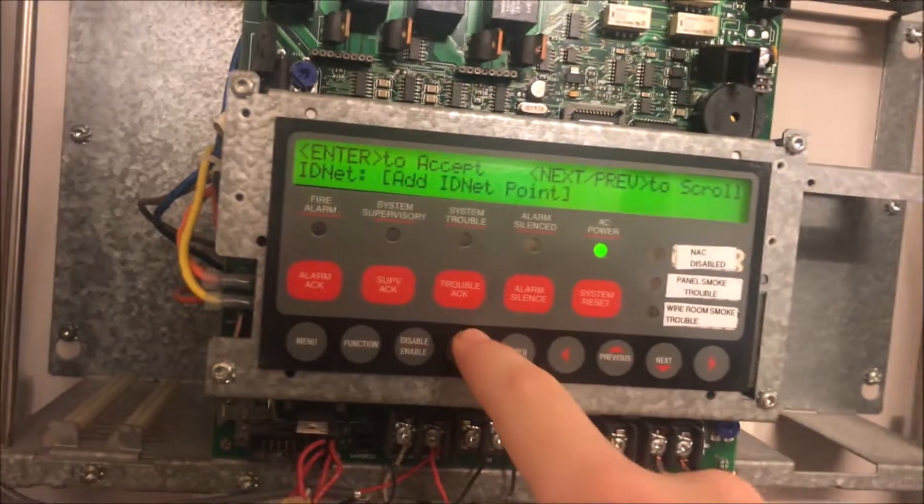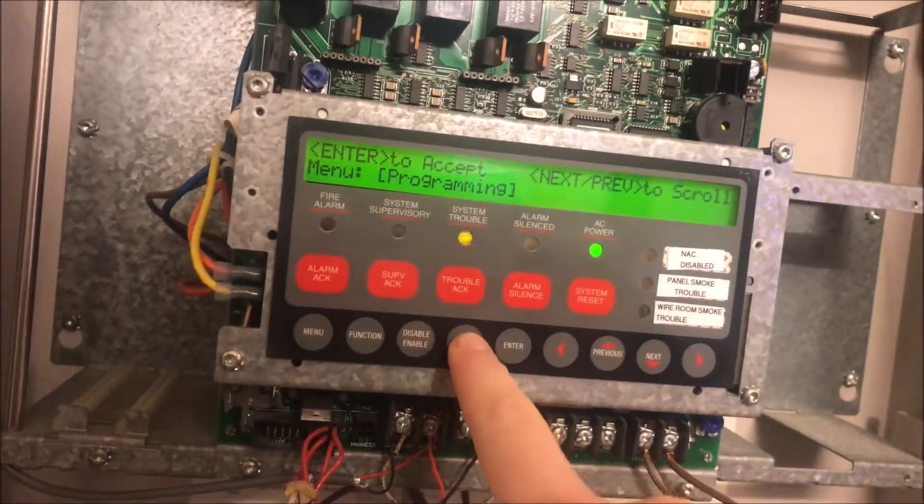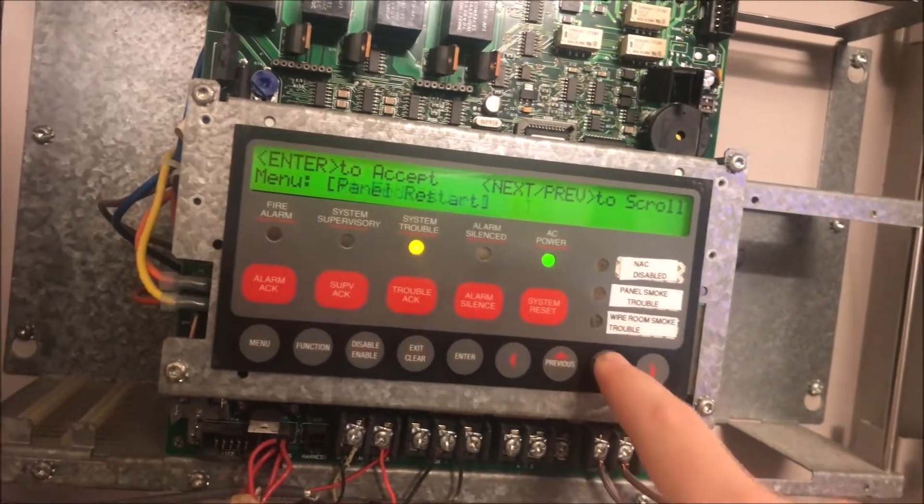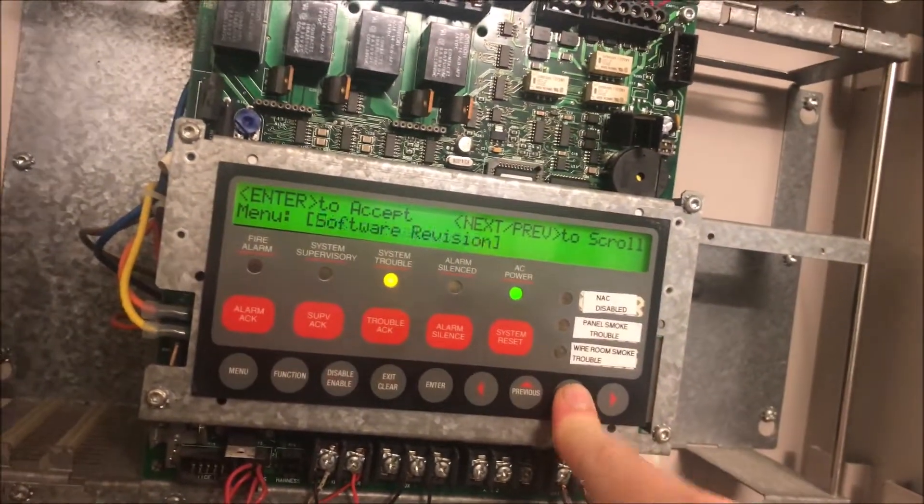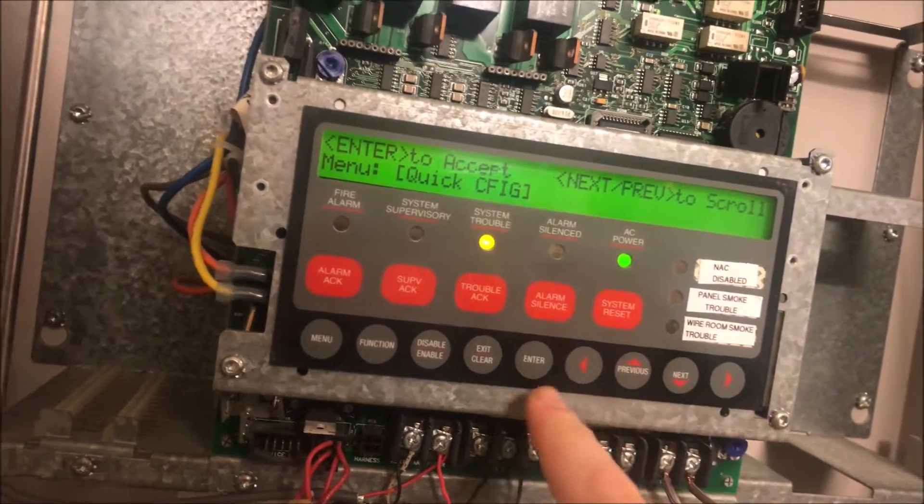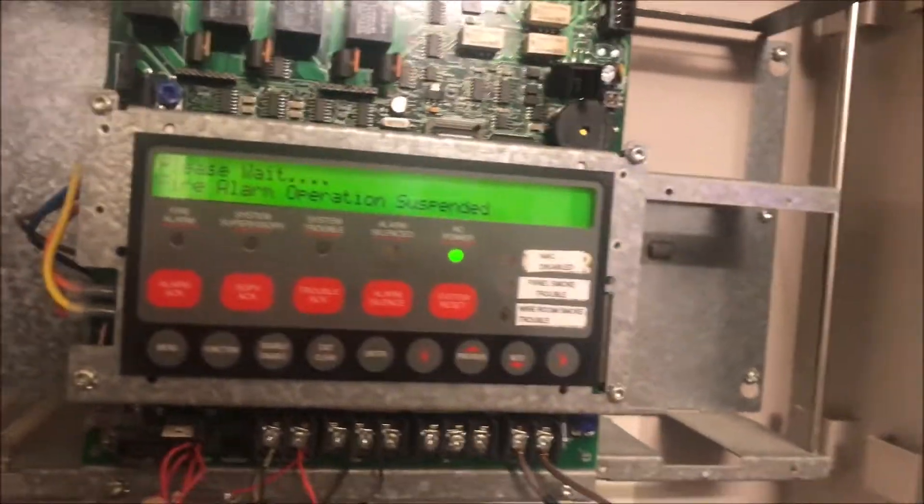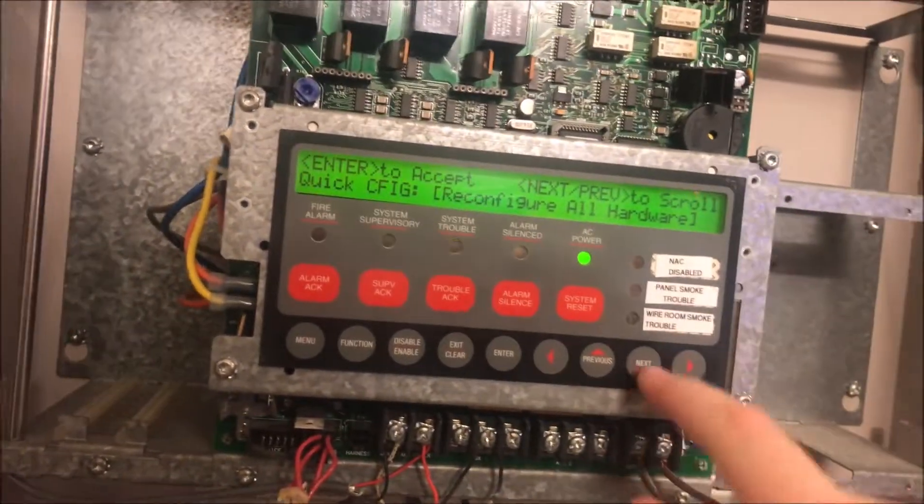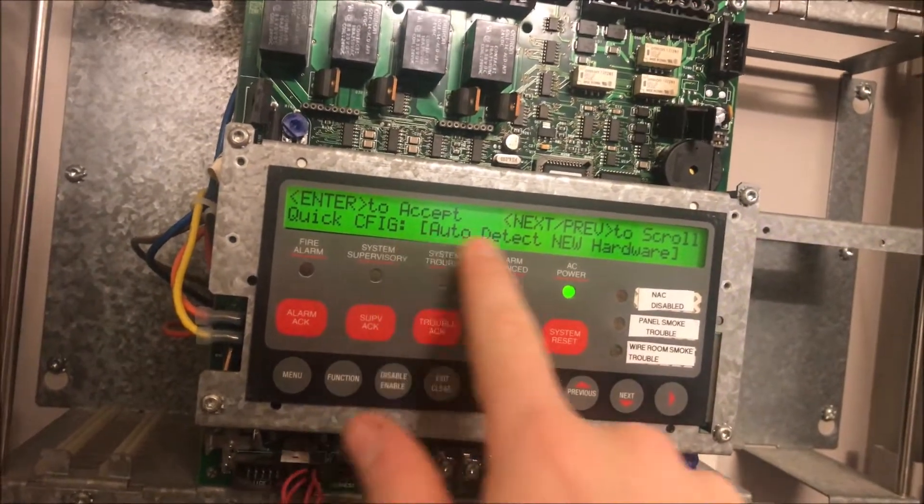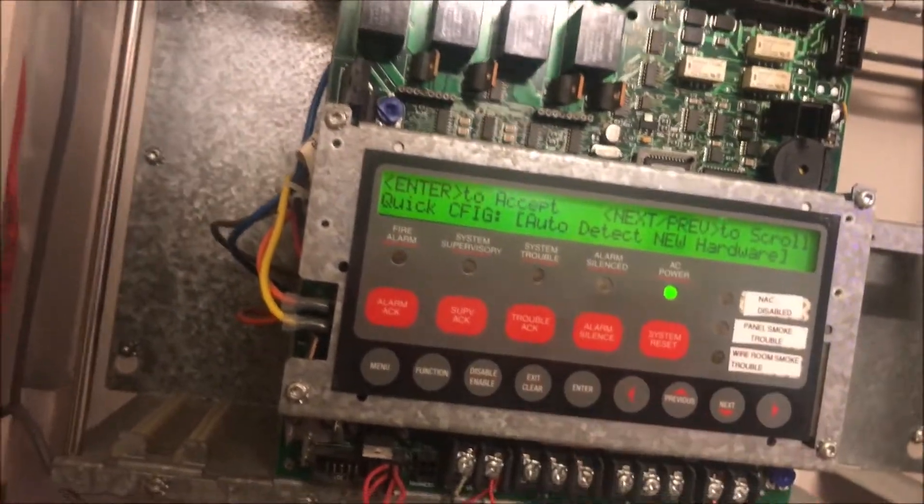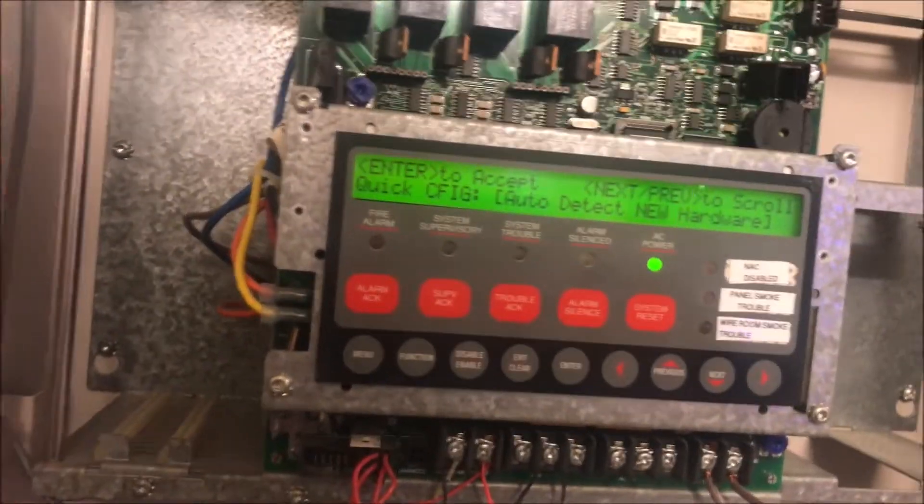Now the second way I'm going to show you - we go to quick config, hit enter. It's going to give us the programming mode trouble again, but because I've already acknowledged it on the annunciator we are good. The easier way, this is how I do it, is you go to auto detect new hardware.